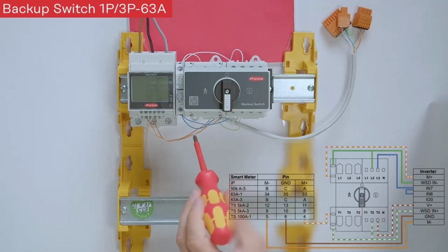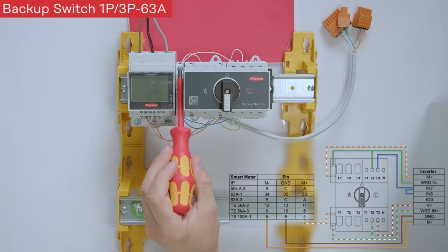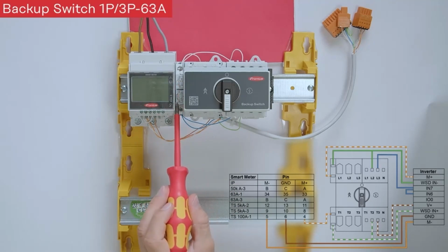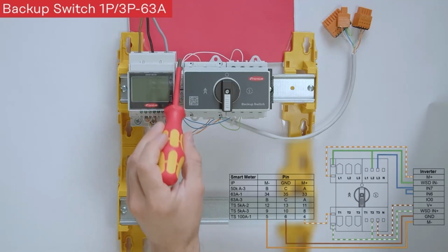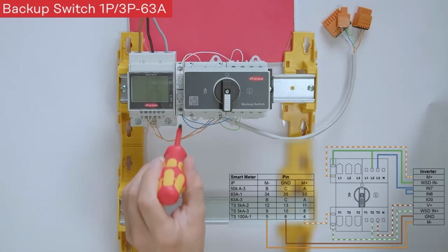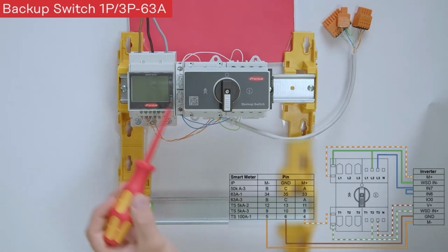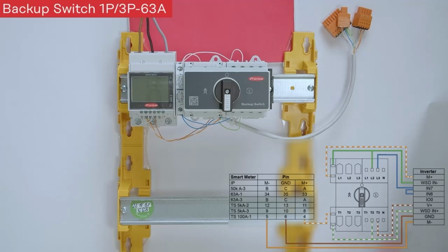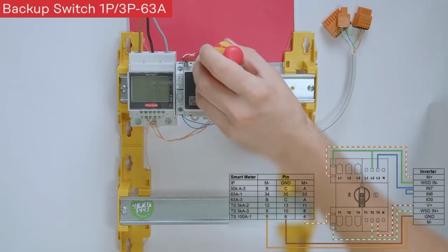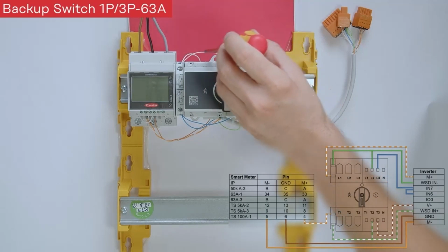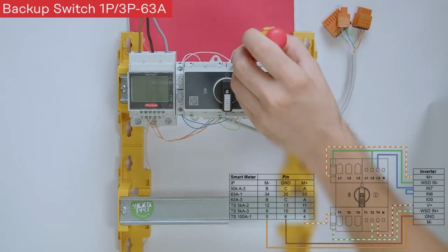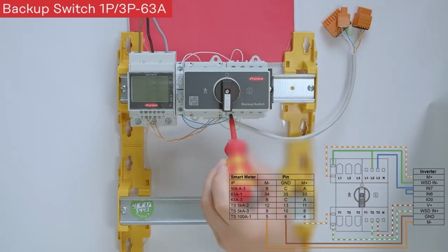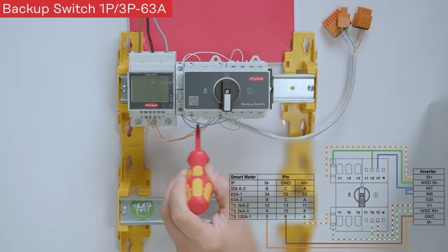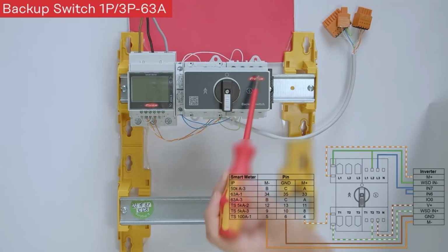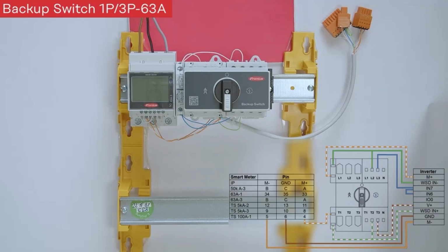So therefore, we are installing our first contact here, the WSD contact, with our auxiliary switch. So the backup switch always includes the auxiliary switch, where you can now install the WSD contact and close it on position number 1. On position number 2, we also want to close this contact, and therefore we can install very easily here, up here, a cable bridge to make sure that here on L1 contact and down below, the cable bridge is closed, so that WSD is closed also in position number 2 in backup power mode.